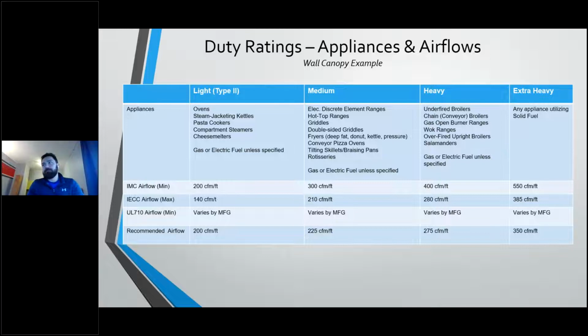Exhaust airflow rates. So this is going to be largely dictated by IMC from the base standpoint. IMC section 507 is going to dictate your hood construction and your capacity of those hoods. First thing to note is kind of an update to IMC: IMC no longer classifies these hoods based on temperature. They used to classify these hoods based on temperature. They've now made it a little bit easier. These hoods are classified just based on a duty rate. So based on light for type 2, medium or heavy, and then extra heavy being for a solid fuel application.